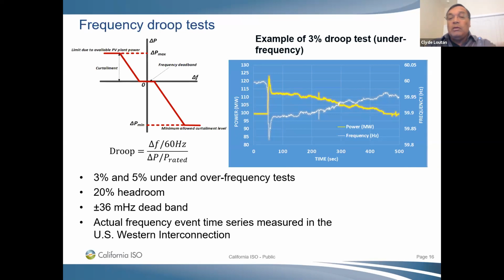And also, what we did is we repeated this test, and on this plot, we looked at a 3% droop. We also looked at a 4% droop and a 5% droop, which shows how well this unit would be able to respond to a droop setting. And then also the deadband, which is when this plant would respond to a frequency deviation. Currently within the US it is 36 millihertz. So within 36 millihertz, the governors do not really react, but for frequency deviation outside that, we get governor action or governor response that helps us control system frequency.